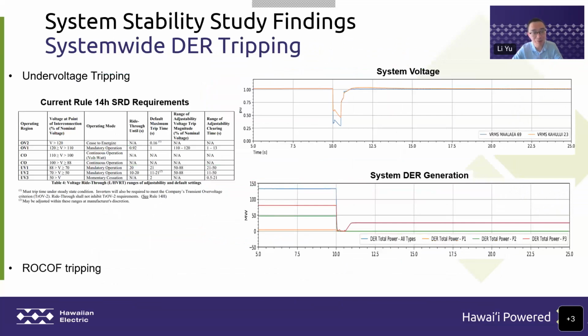Besides system-wide DER momentary cessation, we also see the potential risk of system-wide DER tripping. I want to mention that our system, compared to the mainland system, has a really small footprint. So that basically means everywhere at the transmission level, when we have a fault, especially a three-phase-to-ground fault without any fault impedance, basically the whole system will see this fault. The whole system will experience very low voltages, and that will trigger DER momentary cessation. If that low voltage lasts for a certain time, then we're going to see system-wide DER tripping.